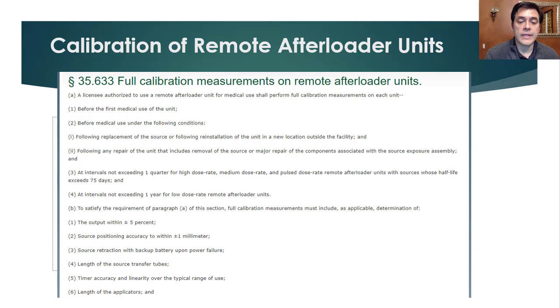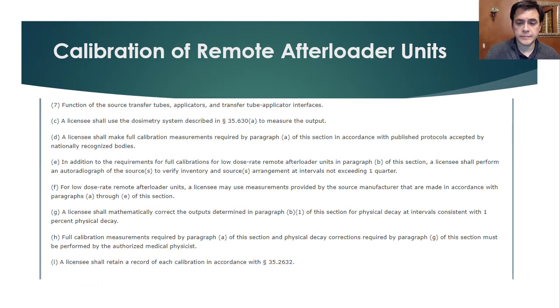The output of the calibration needs to be within 5% of the certified value, and the source positioning accuracy needs to be within 1 millimeter, plus or minus a millimeter. For the source retraction with the battery backup, it should happen upon power failure, and you need to check the length of the source transfer tubes and the timer accuracy and linearity over the typical range of use. The length of the applicators as well as their integrity needs to be checked at each calibration, which hopefully is quarterly, if not quarterly with source exchange, then quarterly without a source exchange.